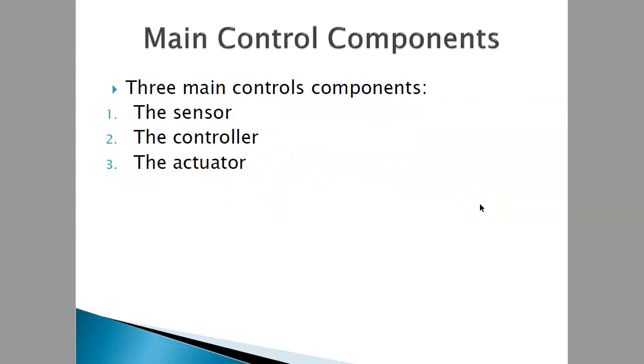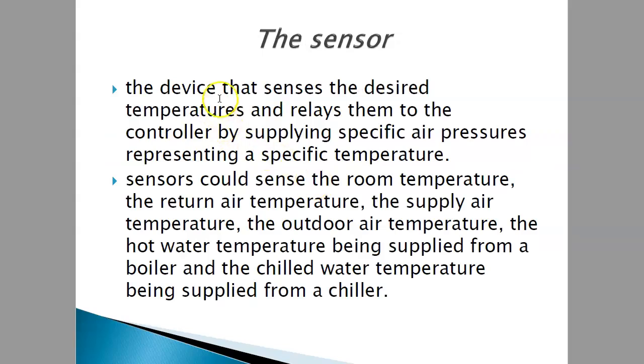Okay, the above slide you could read by yourself. So I directly go to the main control components. There are three main control components, which are the sensor, the controller, and the actuator. So what are the sensors? The sensors are devices that sense desired temperatures and relay them to the controller by supplying specific air pressure representing a specific temperature. So here, for example, it senses air pressure, then the controller will calculate what the temperature is.